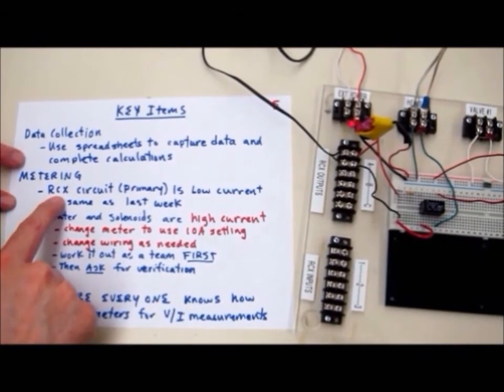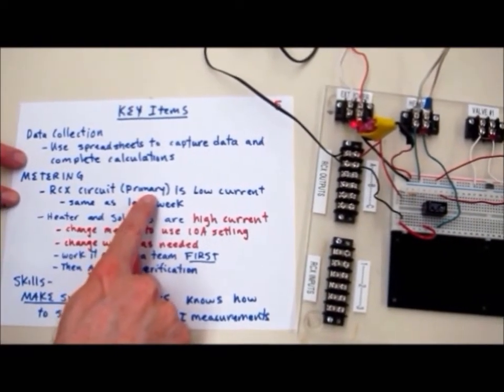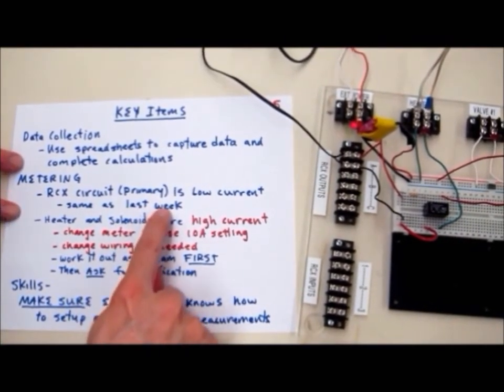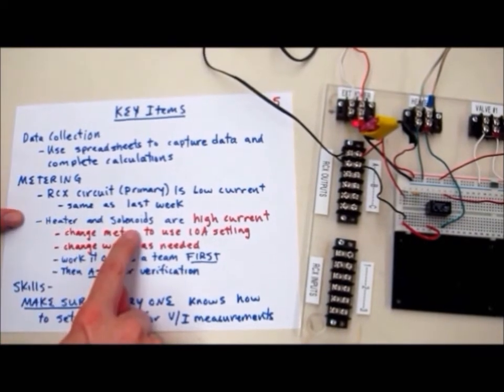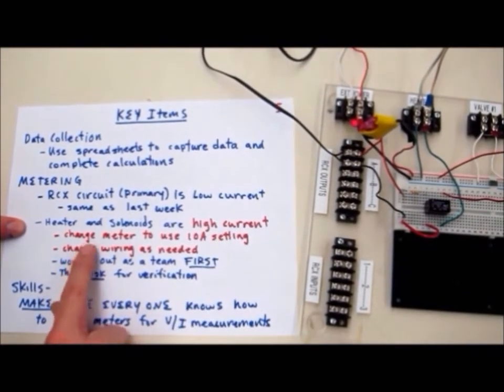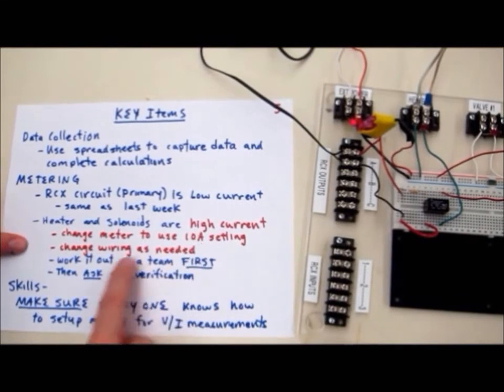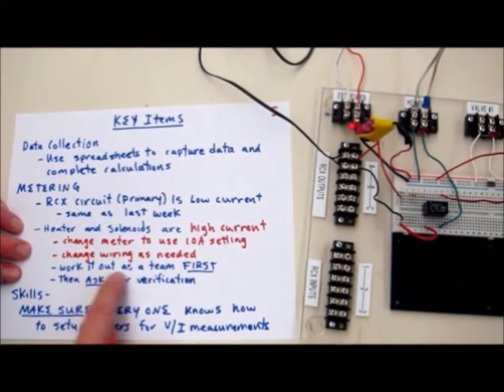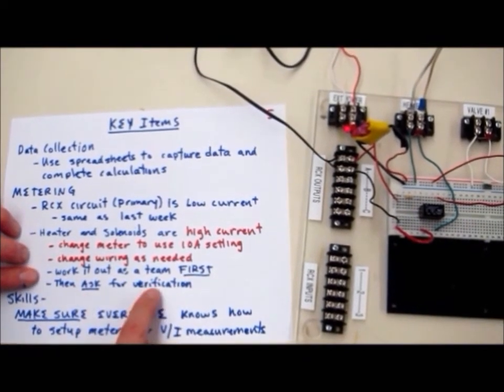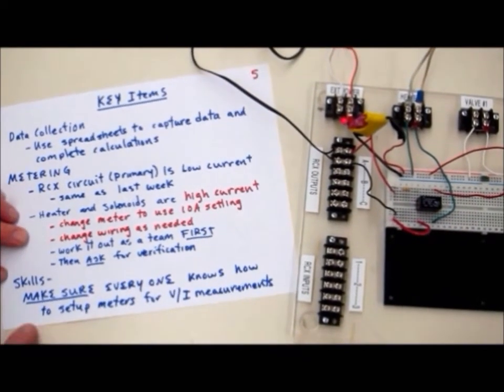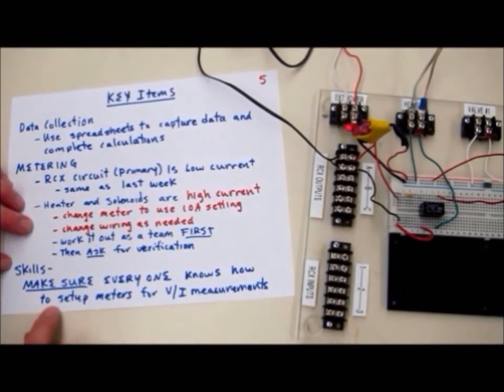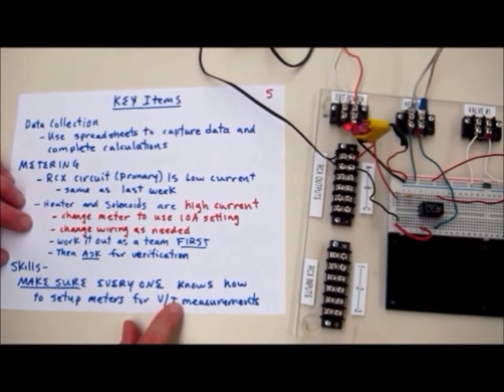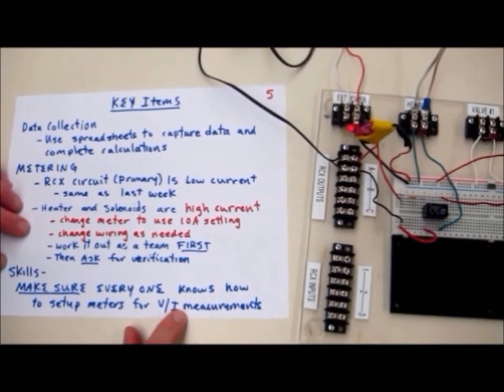In the metering, the RCX, or the primary circuit that we did first, is a low current. It's the same meter connections as last week. The heater and solenoid valves are high current. You need to change the meter to use the 10-amp setting. Change the wiring as needed. We can show you that in class. Work it out as a team first and then ask us for verification. Lastly, make sure everyone knows how to set up the meters for voltage and current measurements. This is a skill we want you to know before you leave this semester. Practice it now and make sure everyone understands.